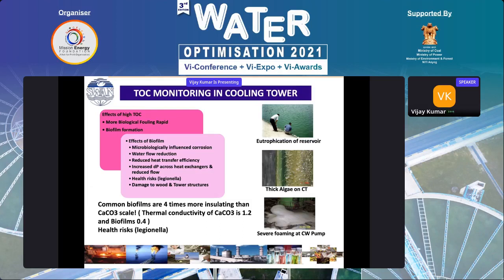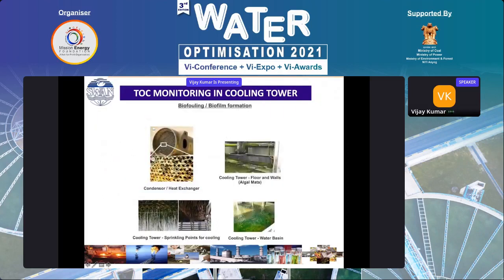The more the biofilm forms, the more severe the effects: microbial influenced corrosion, water flow reduction, reduced heat transfer efficiency, increased delta pressure across heat exchangers and reduced flow, health risks like Legionella bacteria, and damage to the wood and tower structure. And I can say biofilm is four times more insulating than calcium scaling, so you lose your condenser heat exchanger efficiency drastically. If you see eutrophication in the reservoirs or thick algae foaming, these are all indications of high TOC. All these green algae, wood tower structures, everywhere you will find biofilms.